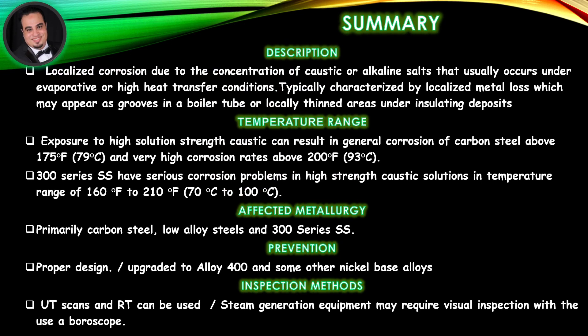Summary — Description: Localized corrosion due to the concentration of caustic or alkaline salts, that usually occurs under evaporative or high heat transfer conditions. Typically characterized by localized metal loss, which may appear as grooves in a boiler tube or locally thinned areas under insulating deposits.